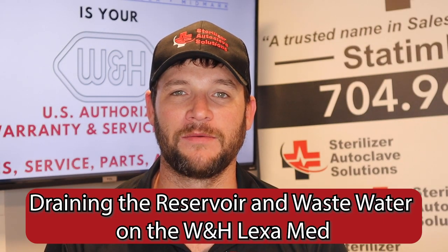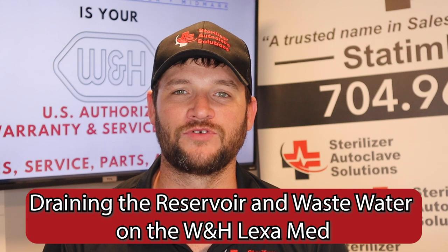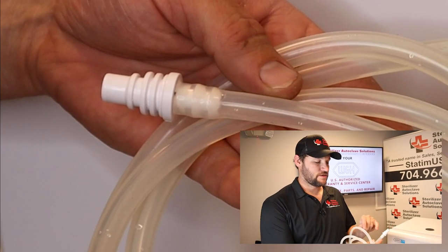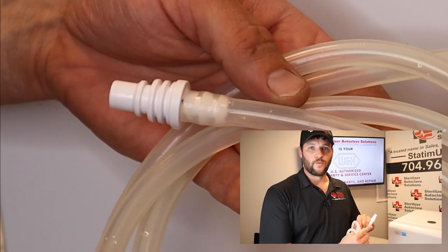Hi, this is Ian with Sterilizer Autoclave Solutions and today we are talking about the W&H Lexa and how to drain the reservoir as well as the wastewater tank. The drain tube for the W&H Lexa has an easy to use quick connect fitting. The water in your clean water reservoir should be drained on a weekly basis, which will help prevent biofilm buildup.